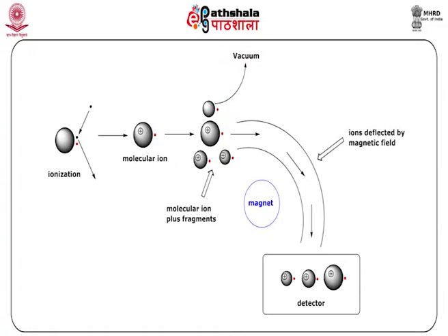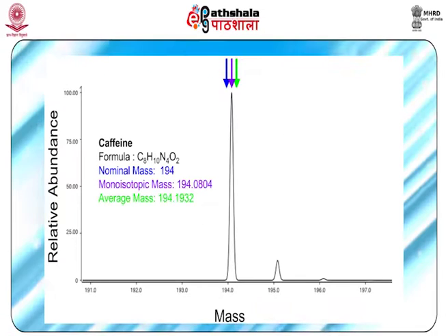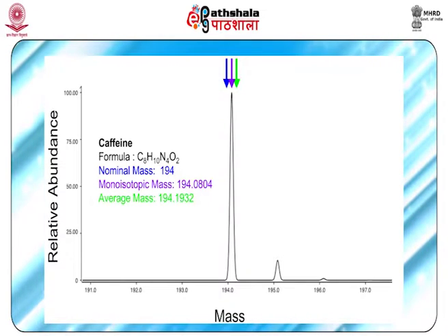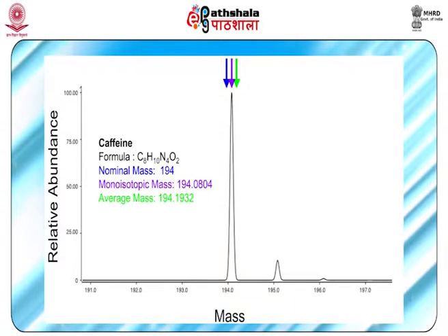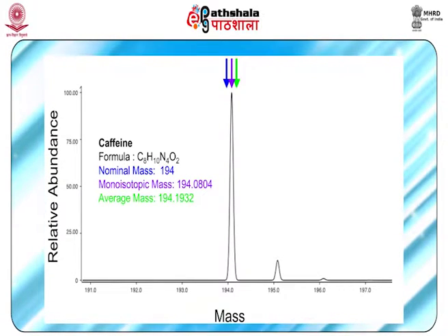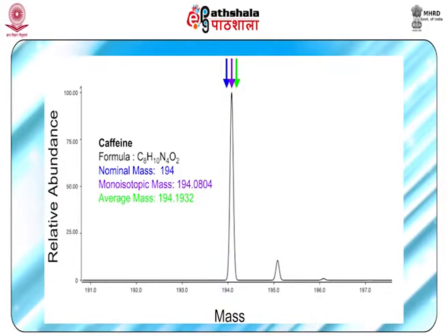These ions are separated in the ratio of their mass with the help of a quadrupole mass analyzer and detected by an electron multiplier. This provides a distinctive pattern of fragmentation which functions as a fingerprint for each compound. For the purpose of identification, the patterns so obtained are then compared to a reference sample.